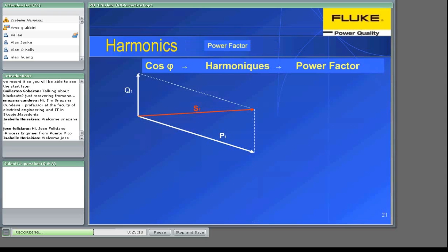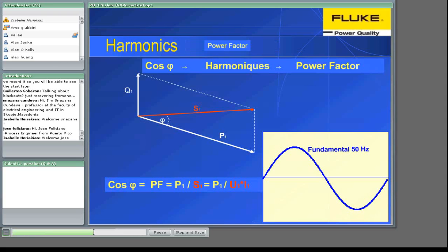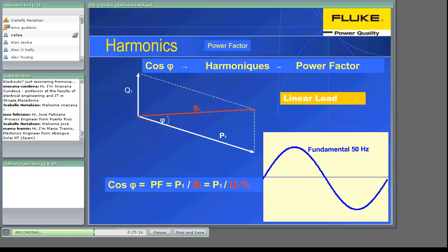The power factor. Harmonics can affect the power factor also. With linear loads only, we used to speak of cosinus phi, which represents the phase angle between current and voltage. It is represented by a bidimensional diagram. The cosinus phi in that case equals the power factor.